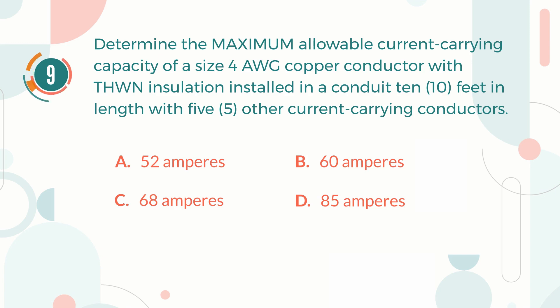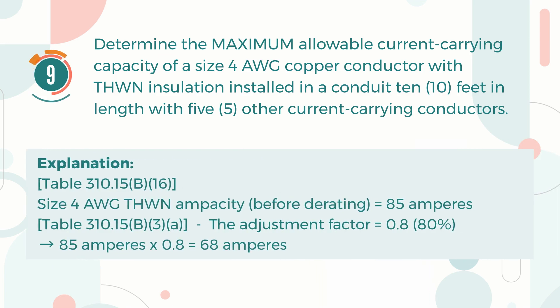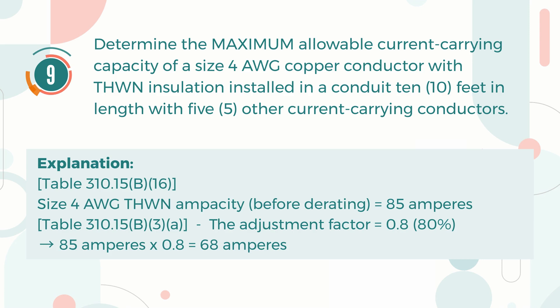The correct answer is C. 68 A. Explanation: Table 310.15(B)(16) indicates that the ampacity of size 4 AWG THWN before derating equals 85 A. Then, looking up the adjustment factor in Table 310.15(B)(3)(a), the adjustment factor is 80% or 0.8. Multiplying 85 A by 0.8 gives the answer of 68 A.